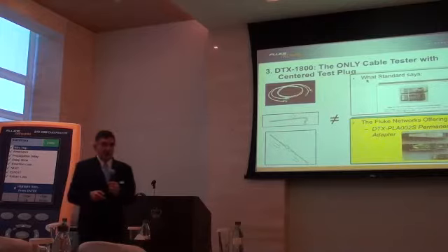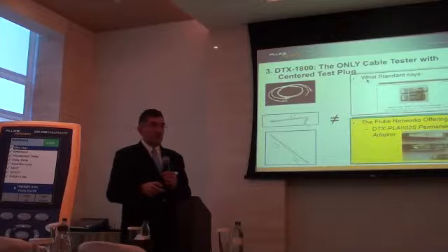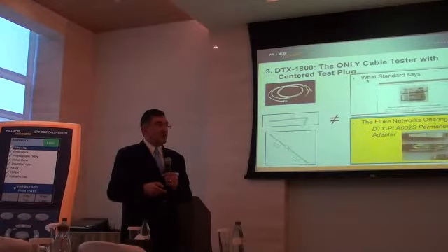It is difficult. Again, coming to the other question, if you certify a link 100%, that it will work up to 100% performance, right? What do you mean by 100% performance? Whatever it is meant for, 10 gig or 1 gig, it will perform that. Now, if we use a patch cord from that supplier or from that cable manufacturer, that will bring the performance down, right? So even if you are certifying it for 1 meg, if the patch cords are not good, it will go down.